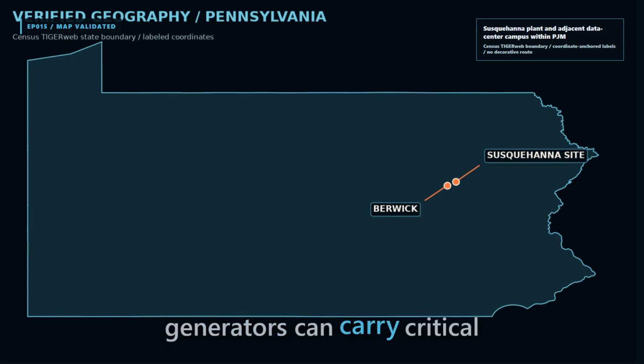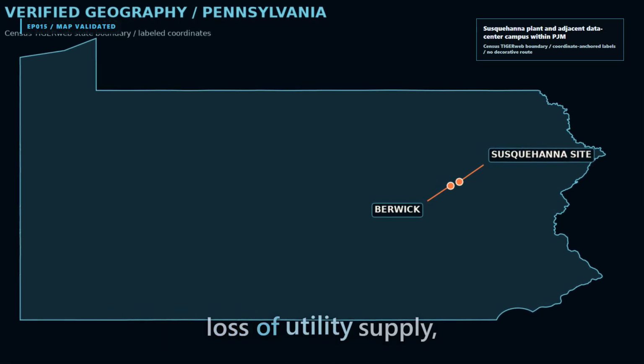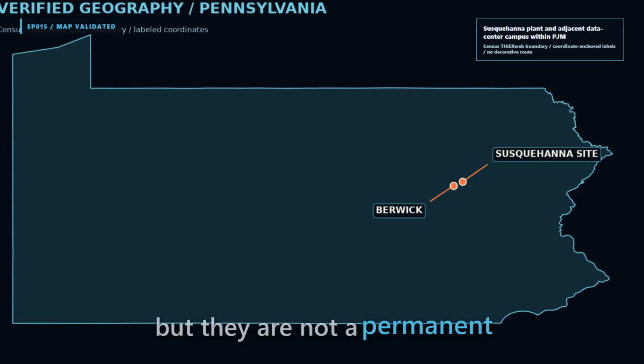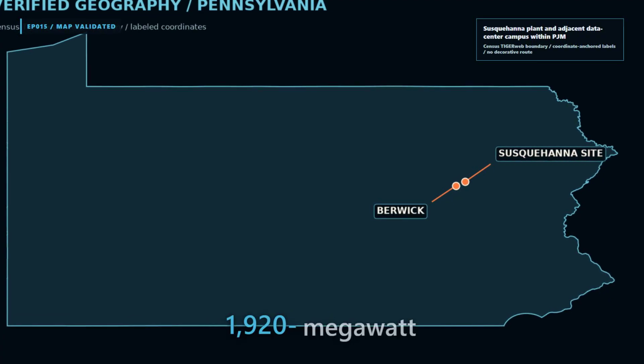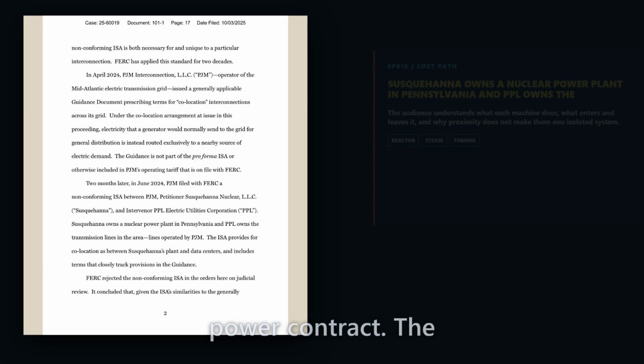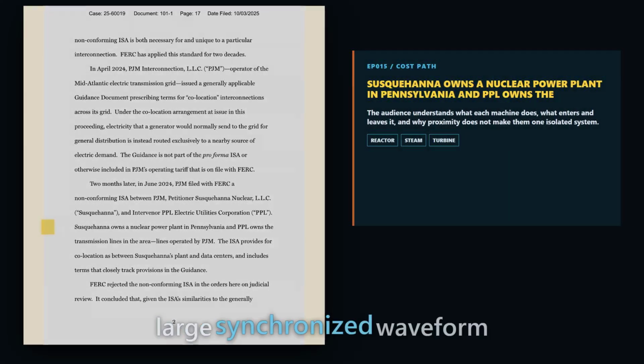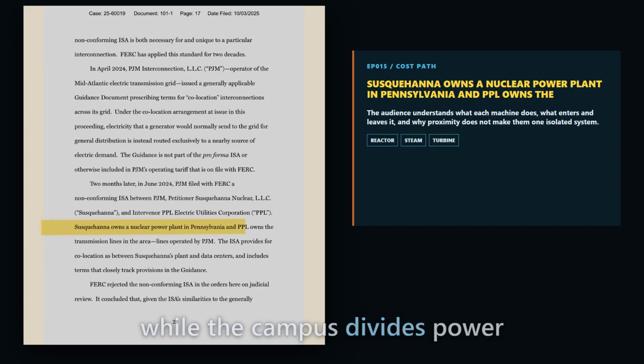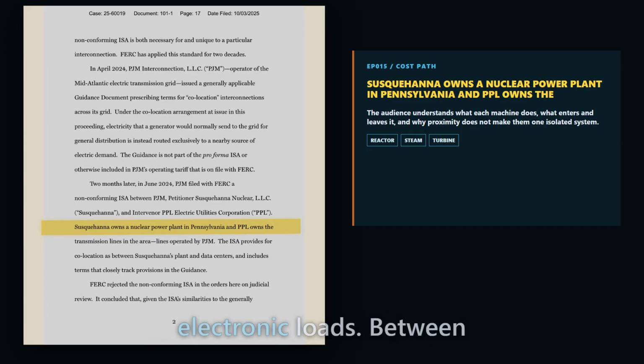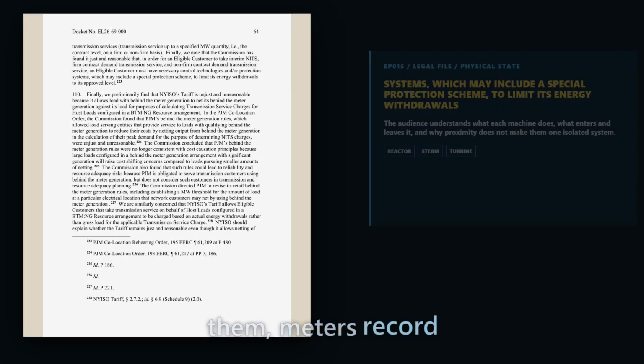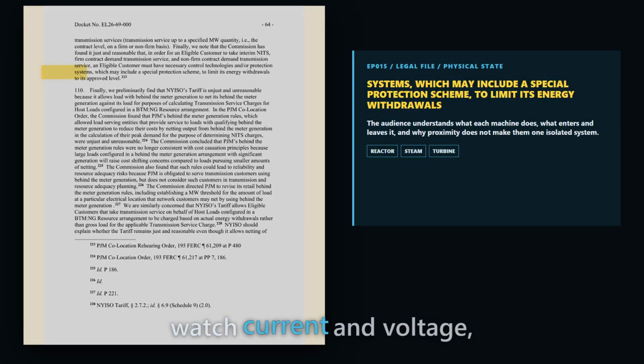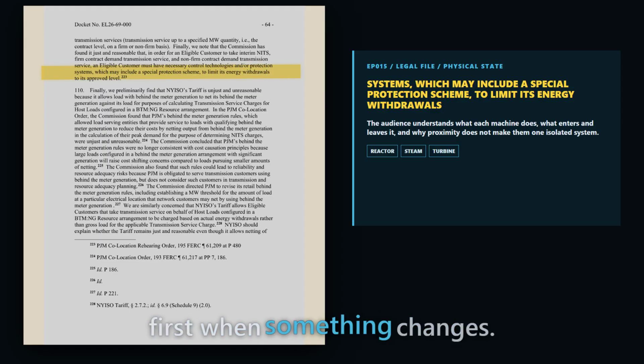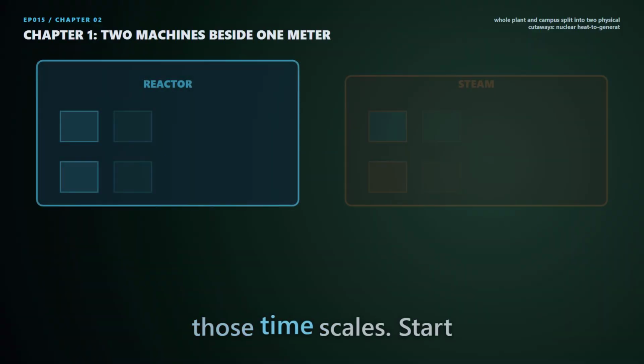Engine generators can carry critical load during a longer loss of utility supply, but they are not a permanent substitute for a 1,920 megawatt power contract. The plant therefore produces one large synchronized waveform while the campus divides power into thousands of controlled electronic loads. Between them, meters record energy, protection systems watch current and voltage, and operators need to know which equipment will respond first when something changes. The grid sits between those time scales.